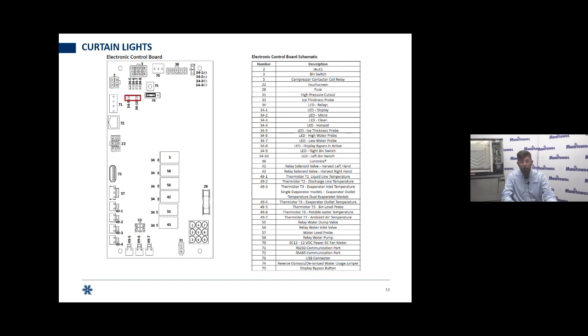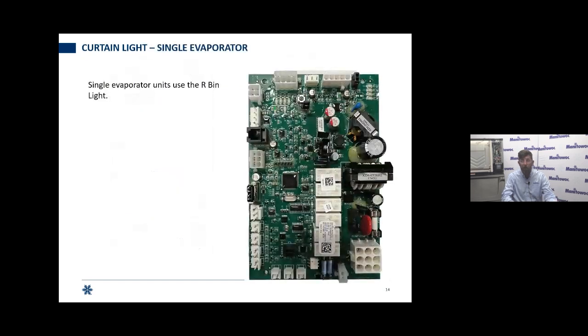Keep in mind, we offer multiple versions, configurations of the Indigo NXT and Indigo ice machine. We have single evaporator, single circuit ice machine, so one plate, one TXV, one harvest valve. We have single plate dual circuit machines, so one evaporator, 2 TXVs, 2 harvest valves, independent circuits, or dual evaporator ice machines, multiple plates, therefore multiple circuits, needing to sense multiple curtains or dampers.